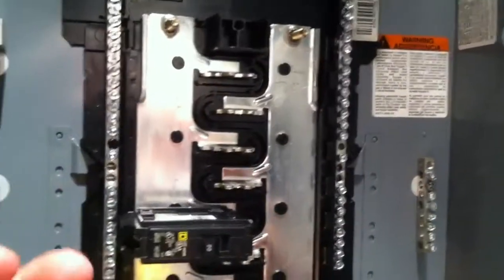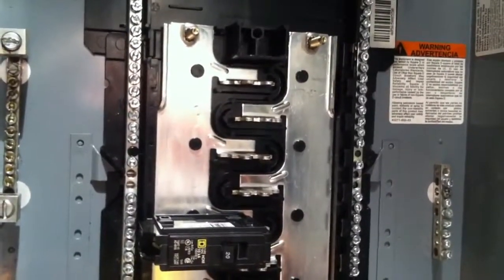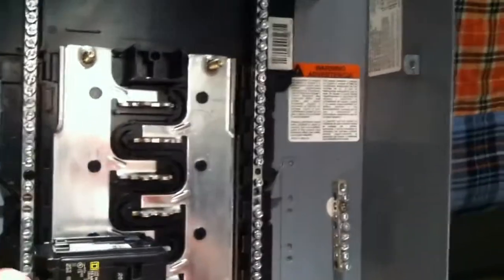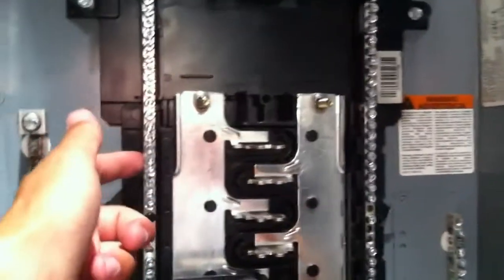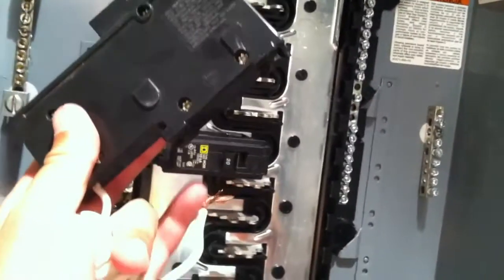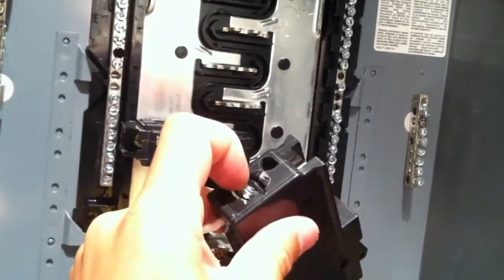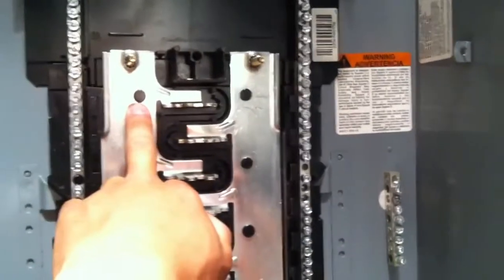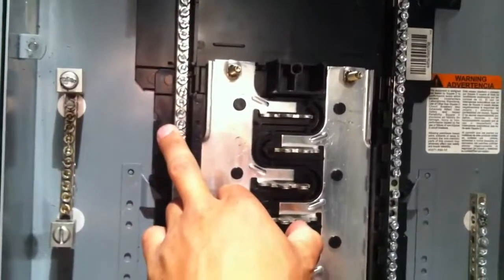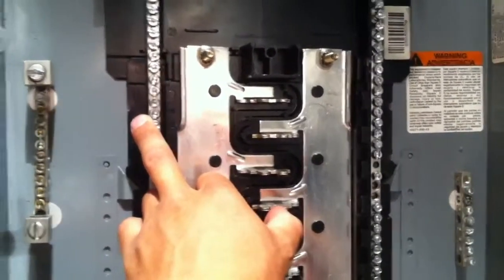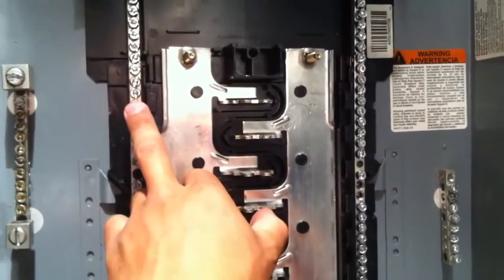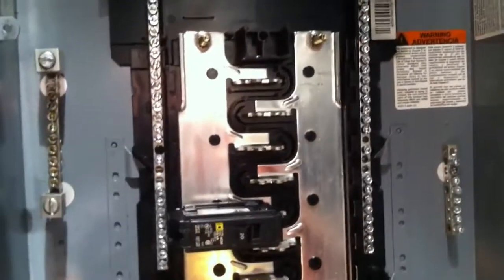It's like you turning on a sink. All the water that comes out of the faucet is going to go into the drain. So what comes out of the faucet goes directly back into the drain. Same thing here. What comes out of this bus bar is going to return through the screw terminal here. Now, this breaker monitors exactly how much is returning through the neutral line, so it finds a difference. If it finds that there's 15 amps coming in through here, but only 14 amps coming back through your neutral, that means an amp of current is going somewhere besides this neutral bus bar. It's going to a grounded circuit, or somewhere else it shouldn't.